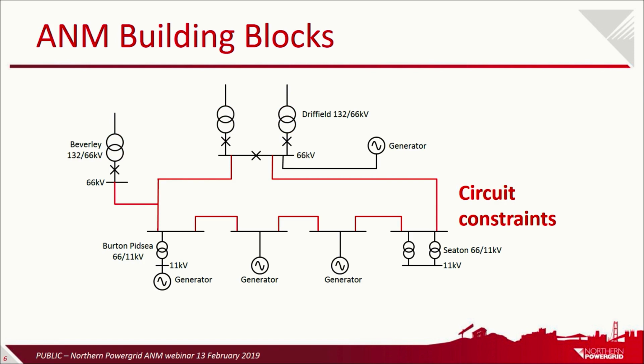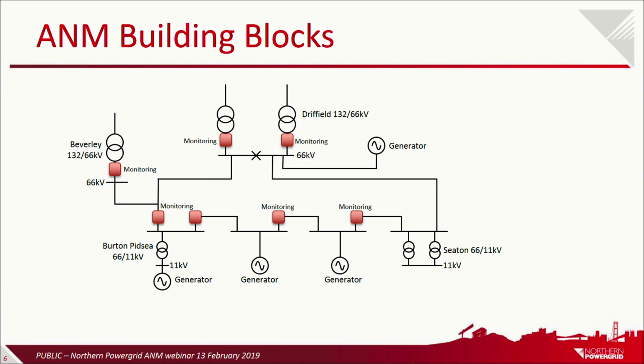We also have some circuit constraints on this bit of the network. So this 66 kV ring system that you can see that's teed off to the Beverley transformer 2, we have some limiting factors on that 66 kV network. So in order to keep power flows within limits on these bits of the network, on the transformers and on the circuits, we need to install some monitoring equipment, which is on screen now. So we'll look at the critical constraint locations on the network and install the monitoring equipment at those locations.